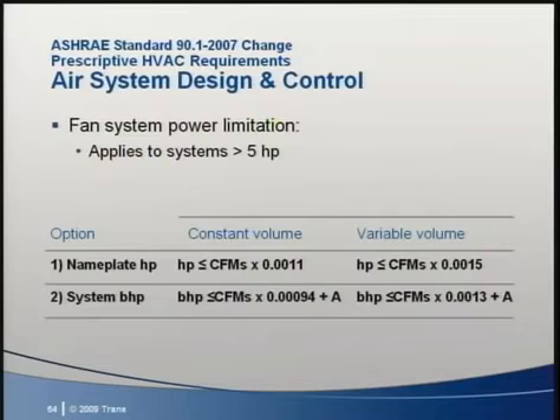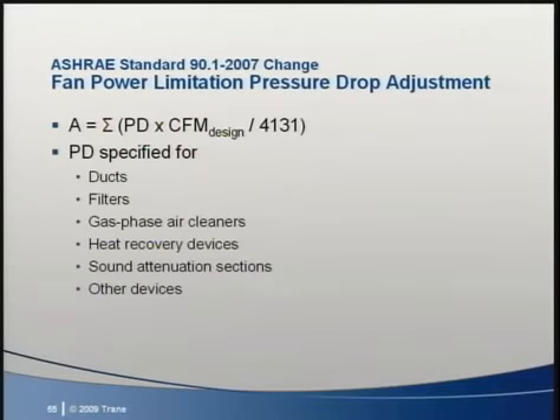The fan power limitation in Standard 90.1/2007 is now based on either nameplate horsepower or system brake horsepower, with the limit shown on the slide. This was done in response to feedback from design engineers. In addition, the standard also defines specific pressure drops that are allowed for a given device in the system. For example, MERV 13 filters are allowed 0.9 inches of pressure drop. This addendum has been well received by practitioners.